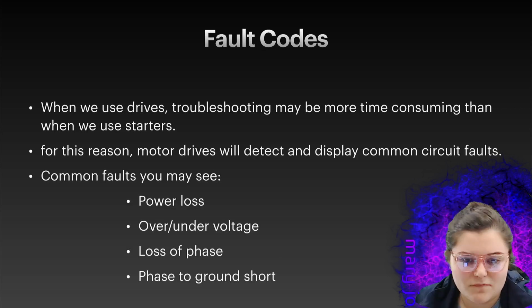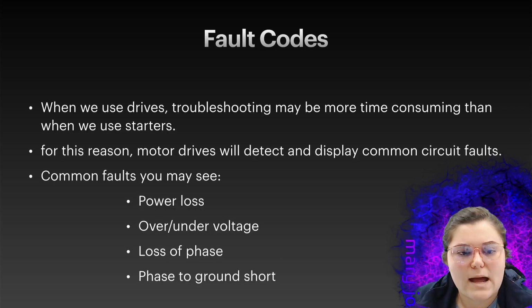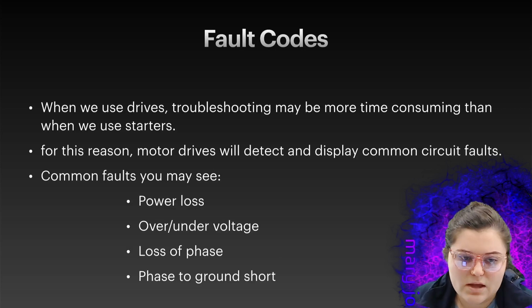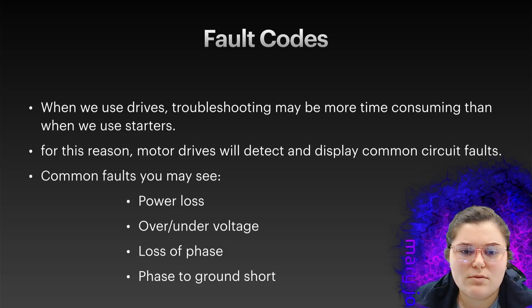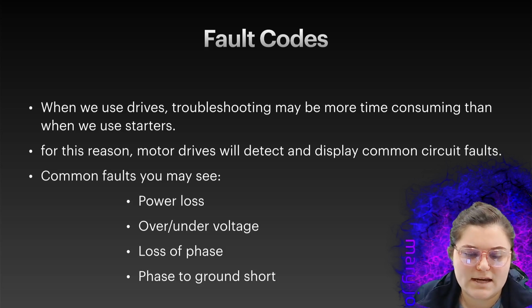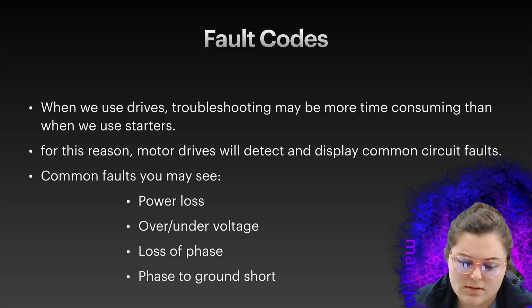And then you'll see some fault codes. When we use drives, troubleshooting might be more time consuming than when we use starters. So for this reason, motor drives will detect and display common circuit faults. Some common faults you may see are power loss, over voltage and under voltage, loss of phase, phase to ground short. So with whatever drive you're working with, you need to be familiar with the faults you may see and what would cause those faults, because that's a good troubleshooting technique, is to look for your faults first.